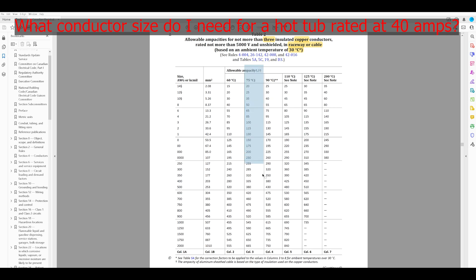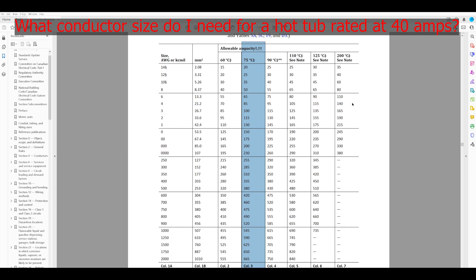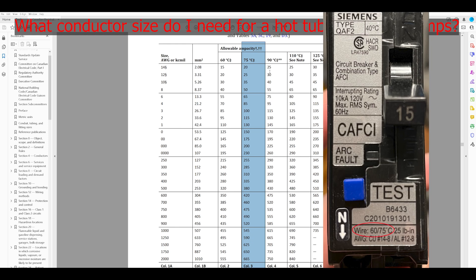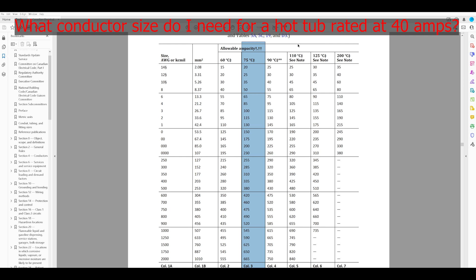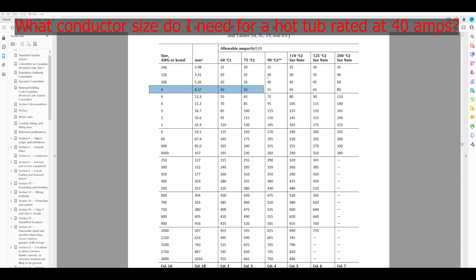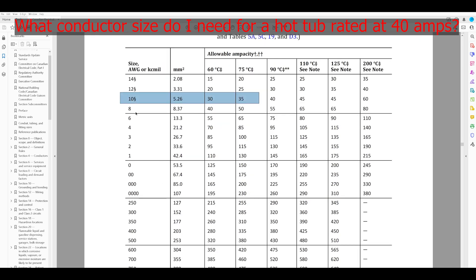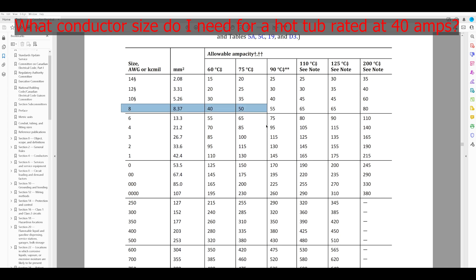Table 2: allowable ampacities for not more than 3 insulated copper conductors, not more than 5,000 volts — that's us. We're in a cable, and basing this on 30-degree ambient temperature. In a residential setting we have to use the 75-degree column, mostly because standard residential breakers are stamped with a termination temperature of 75 degrees — you should always check the side of your breaker. We want to know 40 amps. We don't have a 40, but we have a 50. Number 10 at 35A is not enough. We need at least 40, so a number 8 — good for 50 amps — is the conductor size needed for a hot tub rated at 40 amps.